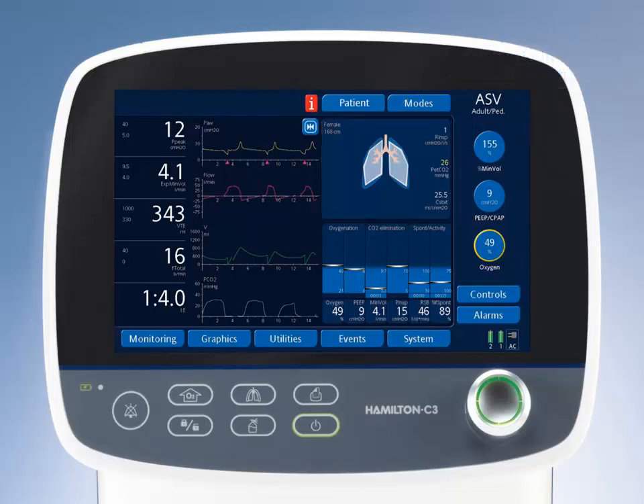In addition, the specially designed alarm lamp at the top of the unit ensures that an alarming ventilator is immediately identified visually in addition to audibly. With the 360-degree alarm lamp, you can immediately identify an alarming ventilator by the alarm lamp at the top, even when you are at a distance or when several devices are operated in the same room.